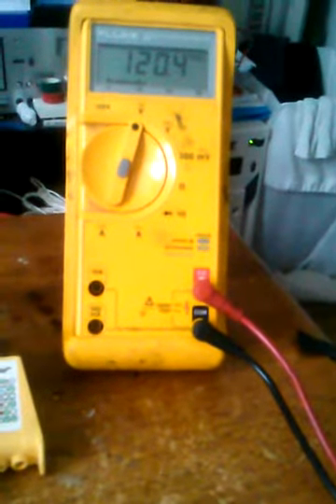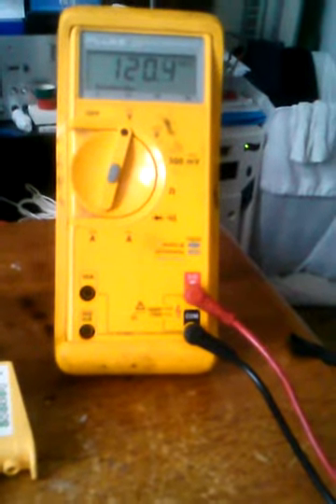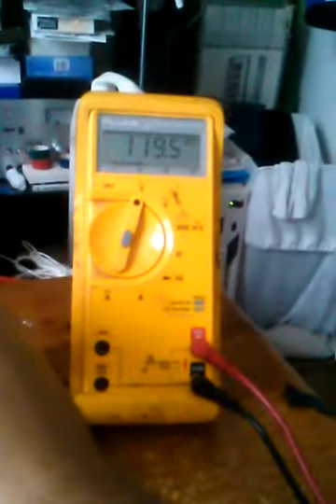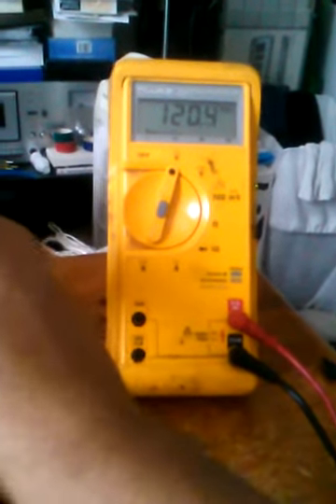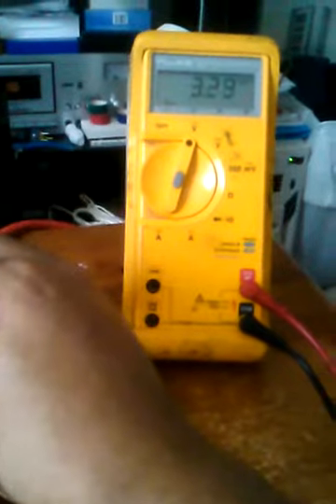on an open ground circuit, you just take one end of the probe, which is your positive side or negative, it doesn't matter with AC. You connect it to this side and you connect this one back to the negative. It should get about 120 volts, which mine reads on the multimeter as 120.4 volts. And the same thing if you reverse it, it should still be 120 volts. Now, if you do the neutral side, which is the longer blade, to ground, it should be about 3 volts.